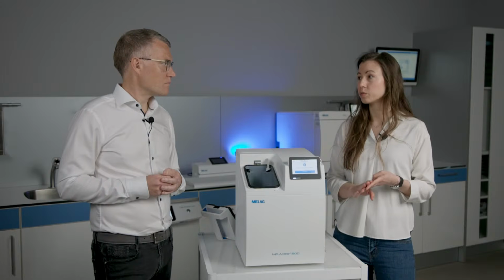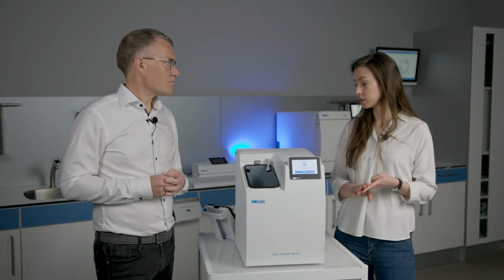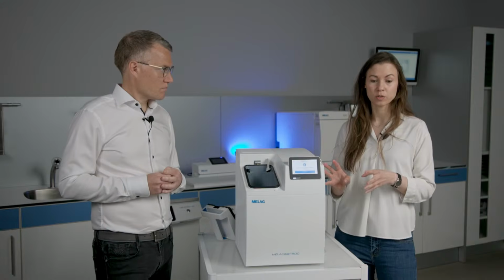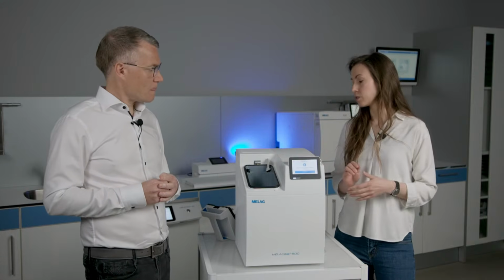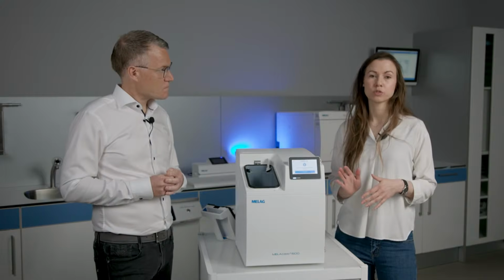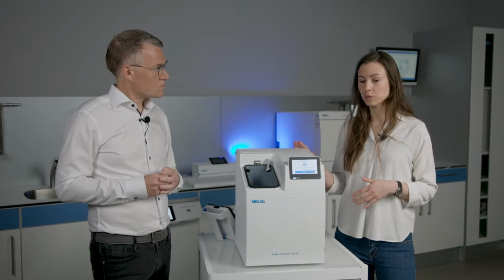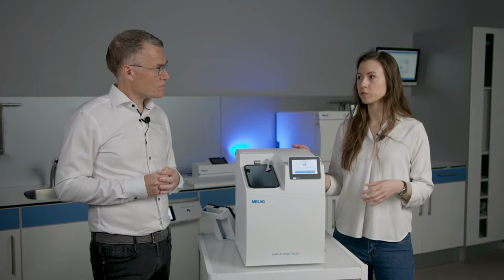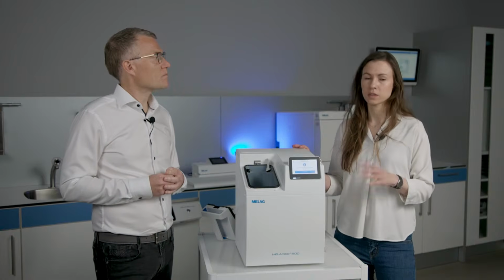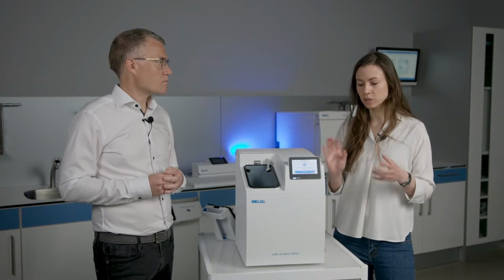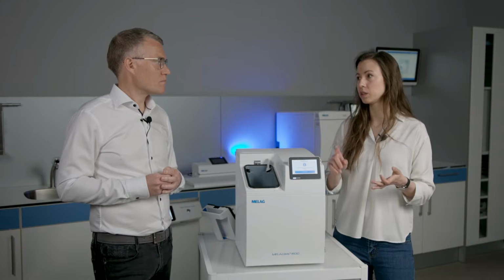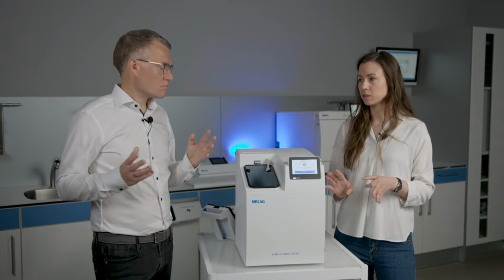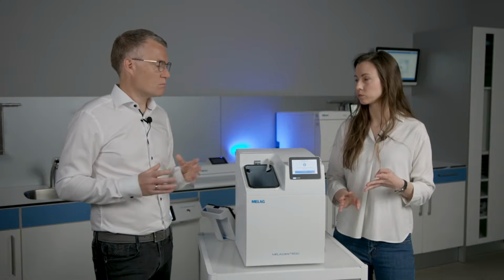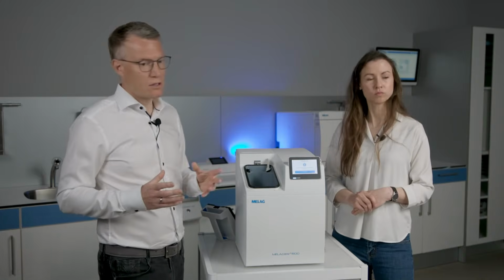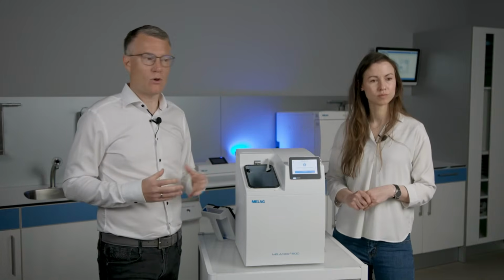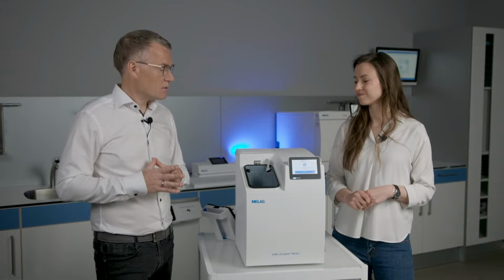Meladem 47 or Meladem 53. That is something that we require, and also a wastewater connection. One alternative solution would be that the MELAG Care can also use external canisters for feed water and wastewater. This is the other option that we have. But in regards to this, you need water, electricity, compressed air, and a wastewater connection. More or less a basic setup, which should be available in almost every sterilization room. Right.